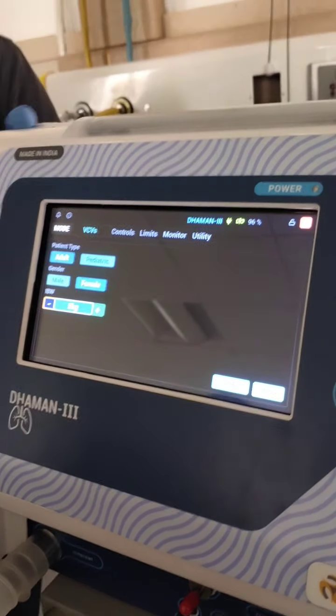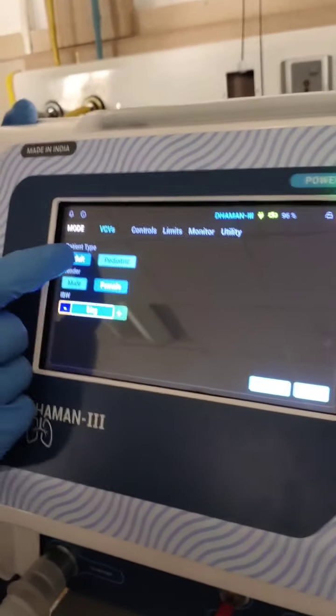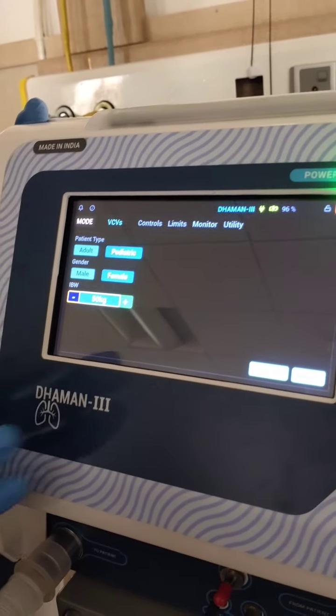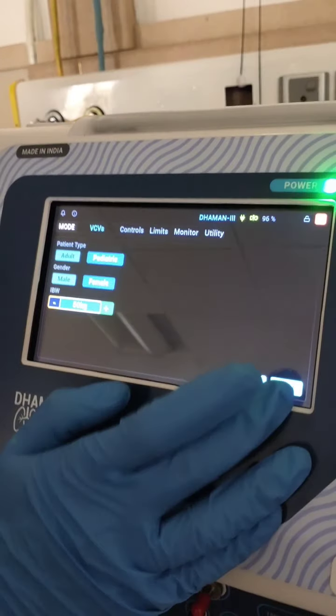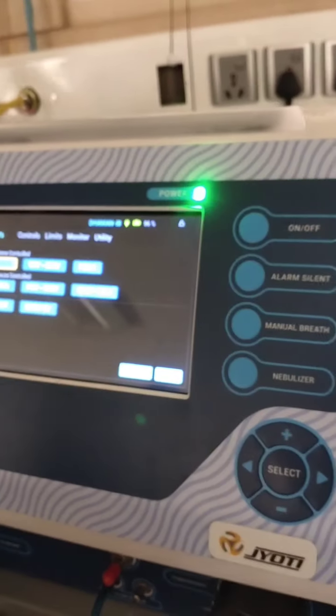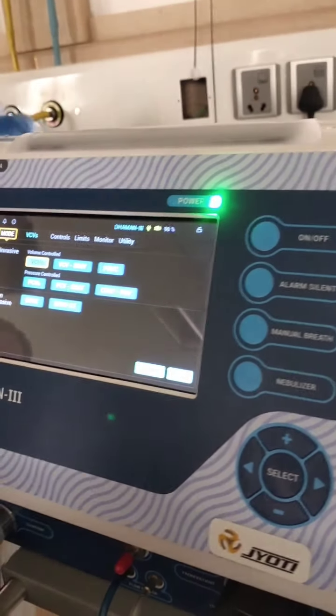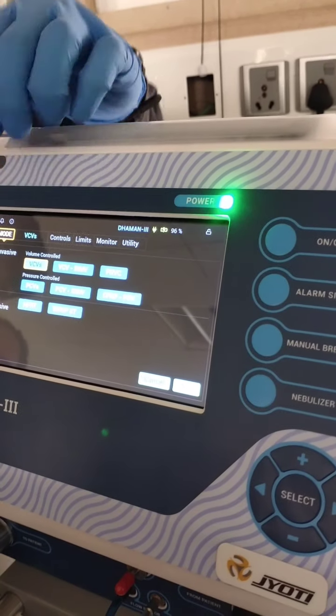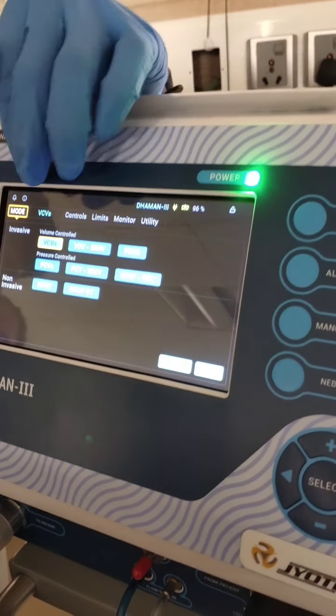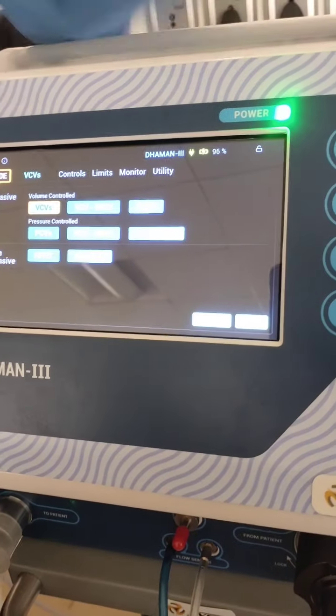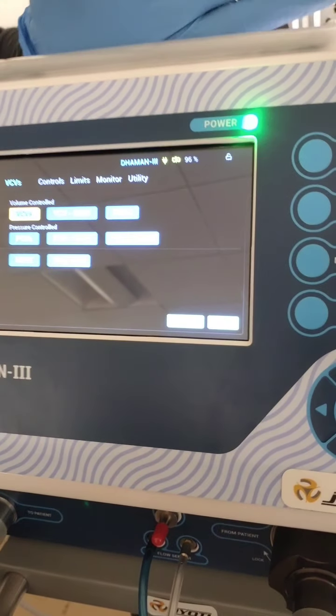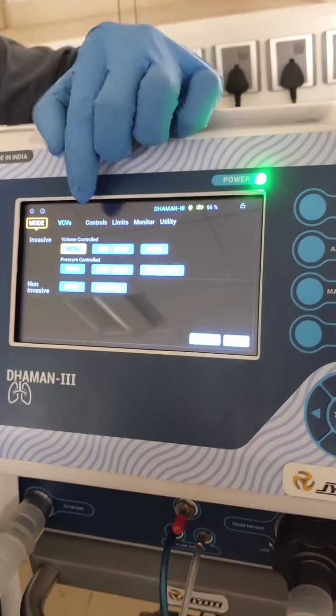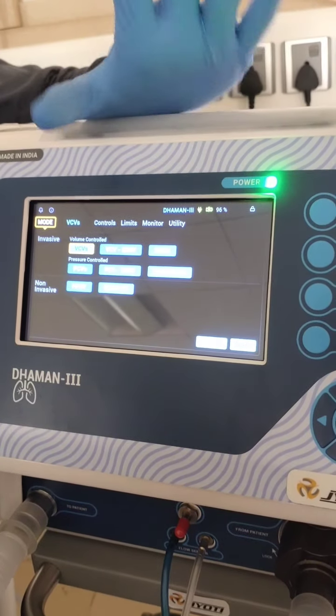Yes, for the pediatric. So now I go for adult, 50 kg. Then go next. Then the mode selection. We have a non-invasive and invasive mode. In the invasive mode we have VCV, volume controlled ventilation, with assisted support and without assisted support also for the same mode. And then volume controlled ventilation in synchronized ventilation, and mandatory ventilation for the second one.